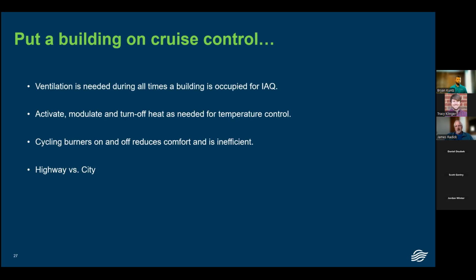I know that happens because I've gone into a few different buildings and seen where our system was in place and they were seeing some stratification. Took a tour of the building and found out that some well-meaning contractor had raised the supply air maximum temperature up to about 120 degrees, which is about the max on this equipment, 110, 120. And so you can imagine the customer's surprise when, after doing a tour of the facility and turning the discharge temperature maximum set point down, they came out of their office and said, wow, what'd you do? The stratification's really better now. Wow, it's gone. What did you do? You can imagine the puzzled looks you get when you say, well, I turned the maximum discharge temperature down.